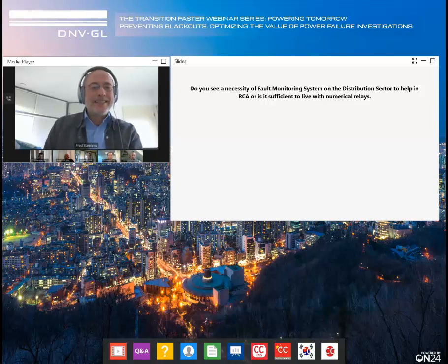Yeah, I'm already starting. Fault monitoring systems we already have in the market for power cables, where we can monitor not only partial discharge activity from weak spots, but also a complete fault, and that goes online. The system, by the way, is called Smart Cable Guard. But that is only for power cables, where we have the ability to locate things that go wrong.